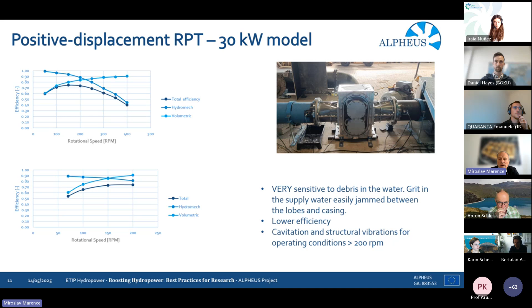But the second major problem is that this system is very sensitive to debris in the water, and any gravel or sand can easily be jammed, or other debris can be jammed between the lobes and casing, and this was seen as a risk. Because of that, this turbine type was not followed further. Also, in the test, cavitation and structural vibrations were observed, and these were the reasons why we concentrated in the project on the counter-rotating reverse pump turbine.